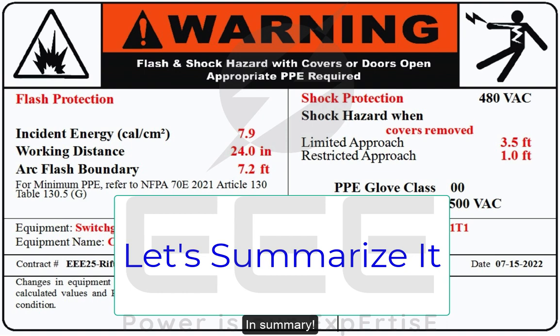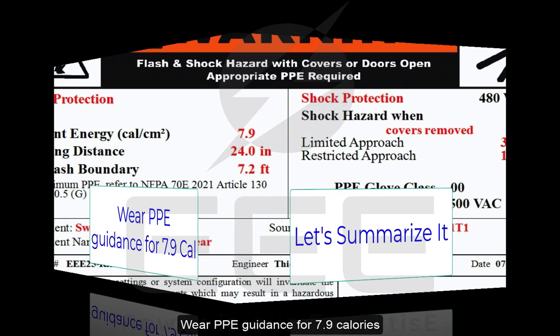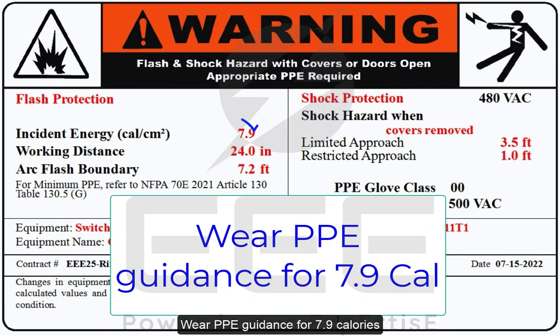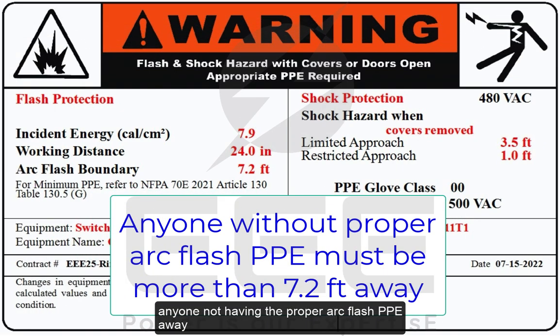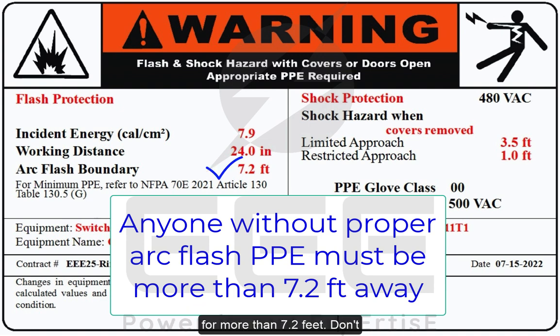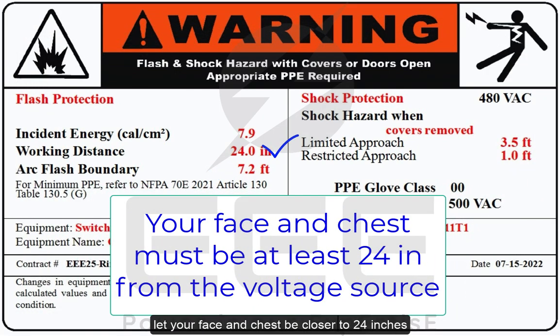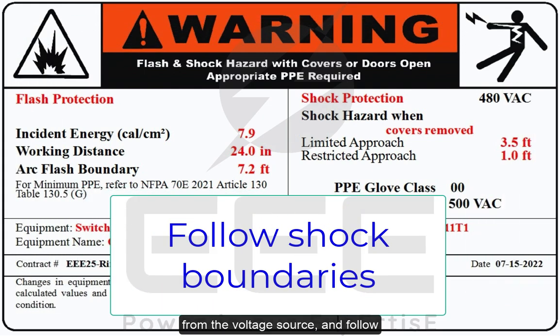In summary, wear PPE guidance for 7.9 calories per centimeter squared or above. Move anyone not having the proper arc flash PPE away, more than 7.2 feet. Don't let your face and chest be closer than 24 inches from the voltage source. And follow shock boundaries and PPE.